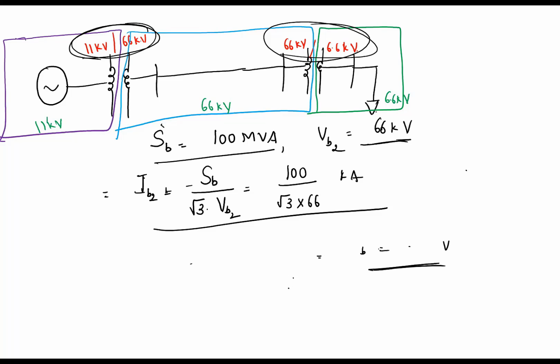Okay. So base current in section 1 will become, the base MVA is same, SB divided by √3 into VB1. That is 100 MVA divided by √3 into base voltage in the first section, 11 kV, so many kiloamperes. So identically you can calculate the base current in the third section. So one thing you have to remember, the base MVA for the entire power system network is the same, but base voltage and base current values will change. Okay.